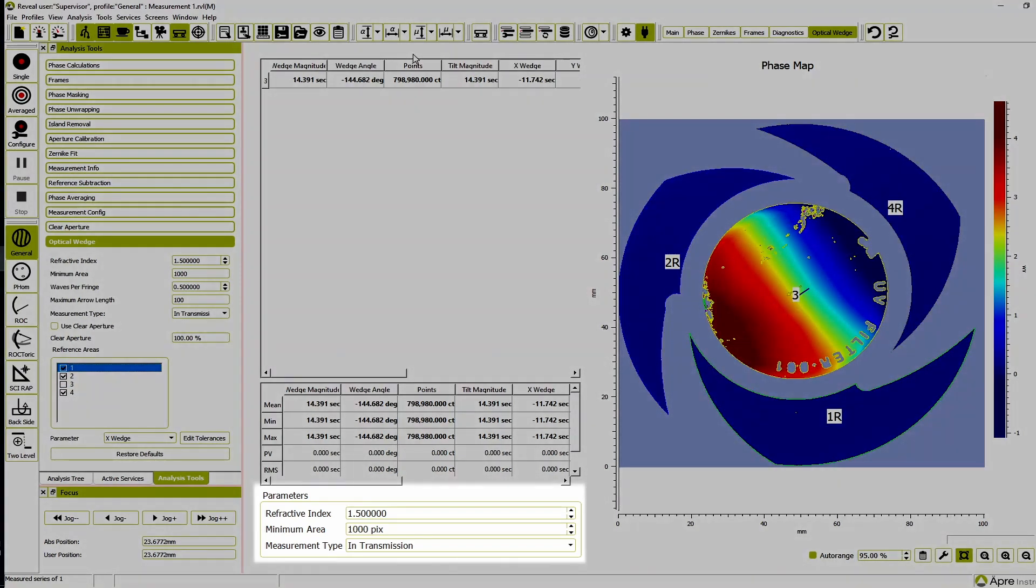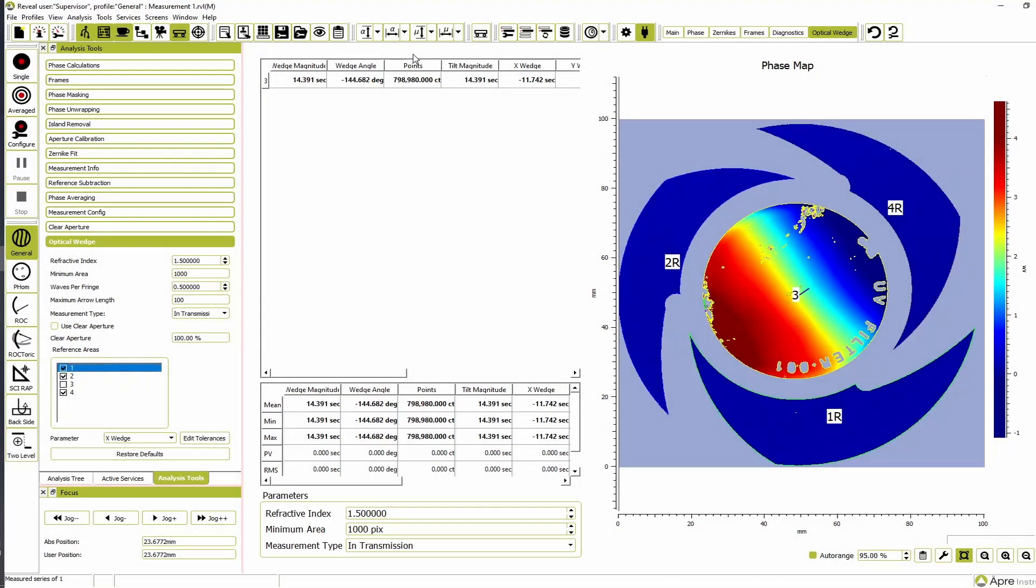Enter the index of refraction of the part and select the correct measurement type. Reveal will automatically calculate all of the wedge results including wedge magnitude and angle and the tilt magnitude and angle.